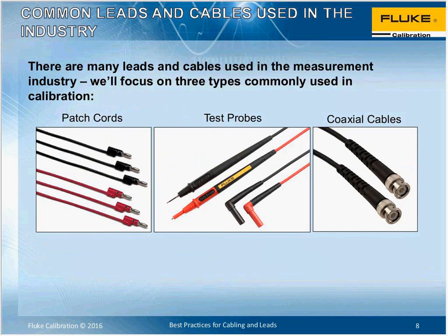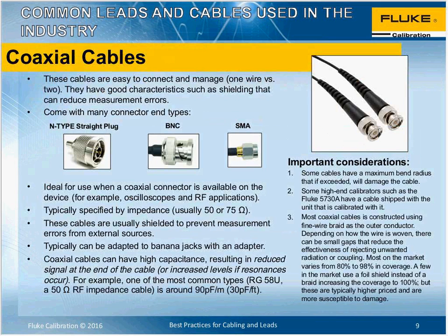And coaxial cables. So we'll start off here. These types of cables are easy to connect and manage. They do typically have good shielding that can reduce your measurement errors. Now, typically you'll find that they come with 1 of 3 types of plugs, and there are many various ways that you can order or obtain these. Some with N-type on one end, and BNC on the other, or SMA type, but they are adaptable. So you'll see one of those 3 types of connections. Typically, on our high-end calibrators, such as our 5790, which is our AC measurement standard, we have an N-type plug out the front of that device, and that allows for direct, easy connections to other devices.